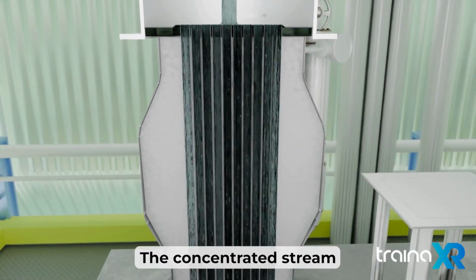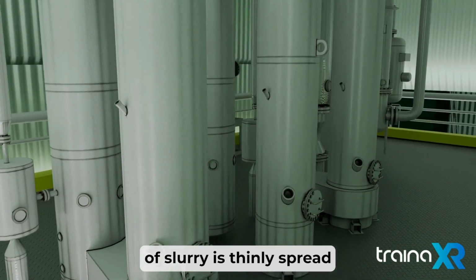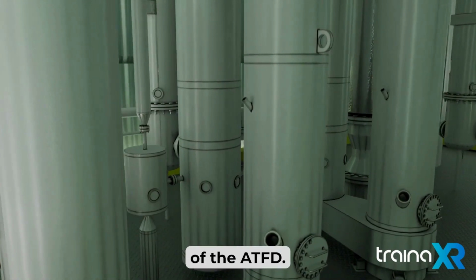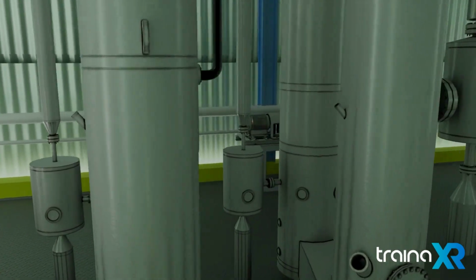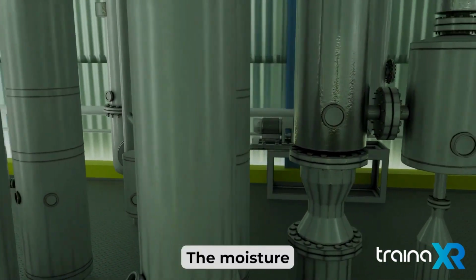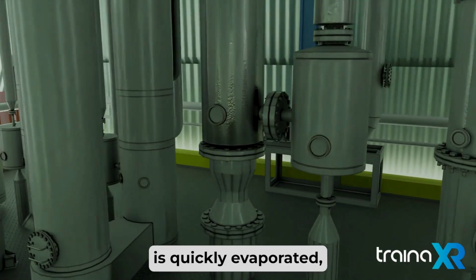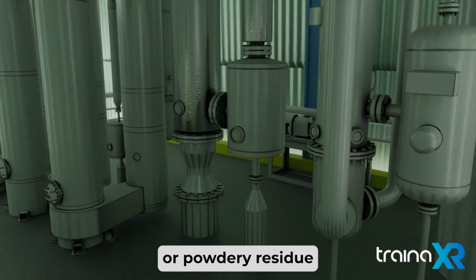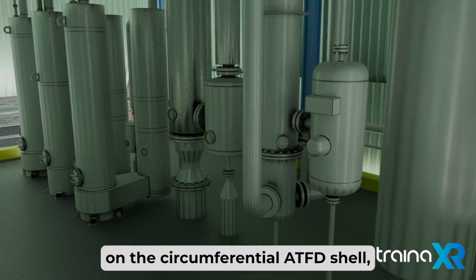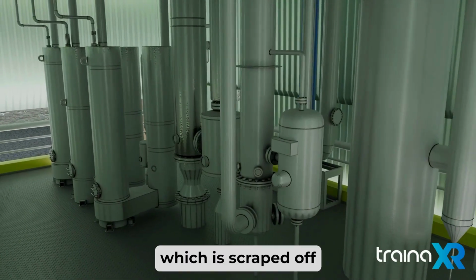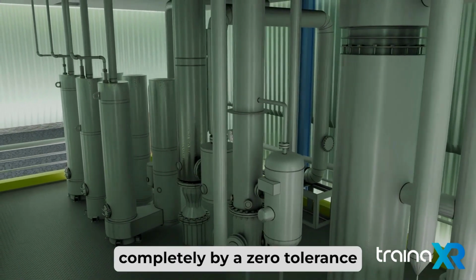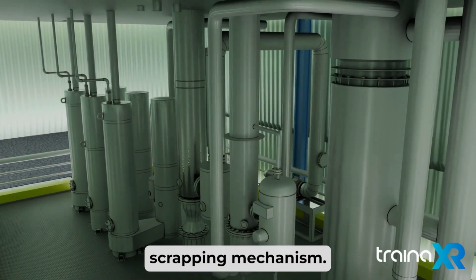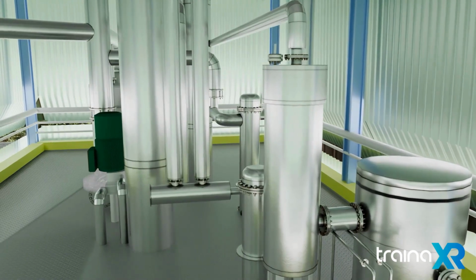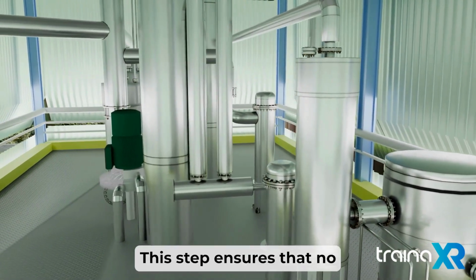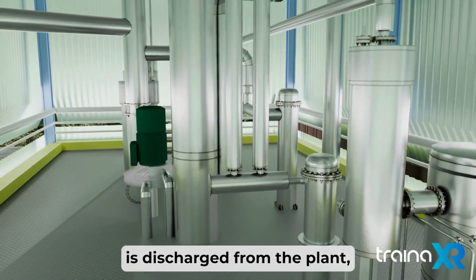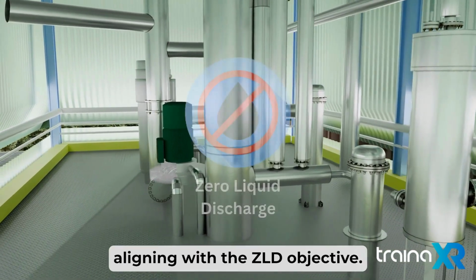The concentrated stream of slurry is thinly spread across the periphery of the ATFD. The moisture is quickly evaporated, leaving behind dry salts or powdery residue on the circumferential ATFD shell, which is scraped off completely by a zero-tolerance scraping mechanism. This step ensures that no liquid waste is discharged from the plant, aligning with the ZLD objective.